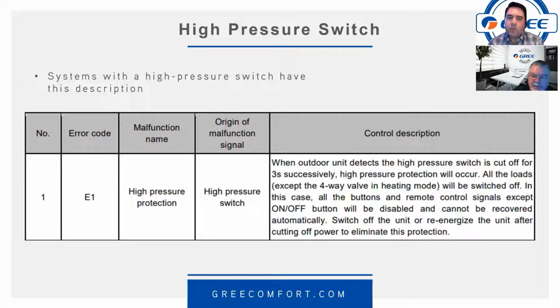The reversing valve will continue to be energized. In this case, all the buttons on the remote, except on and off, will be disabled, cannot be recovered automatically. Switch off the unit and re-energize after cutting off power to eliminate this protection. Well, it doesn't eliminate it. It doesn't fix it, right? Cutting off power doesn't solve the problem. It just clears it until the problem displays itself again.